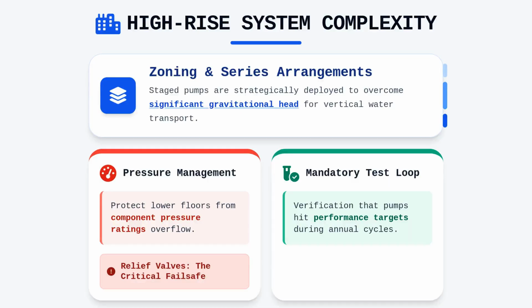Furthermore, the test loop is not just an optional component. It is a mandatory requirement for verification that the pump can actually hit its performance targets during the annual inspection and testing cycle. By maintaining these rigorous installation and maintenance protocols, we ensure that the mechanical response is instantaneous and that the hydraulic integrity of the fire protection system remains steadfast under the most severe conditions imaginable.